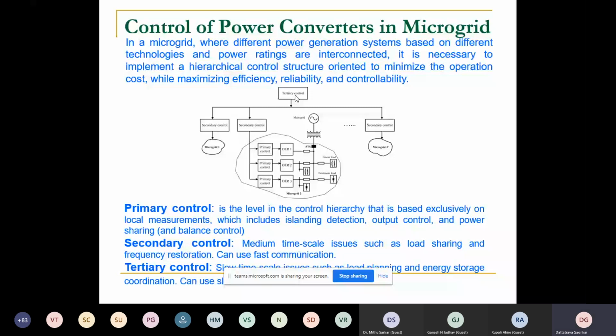So how do you do primary control? As you know, power electronic based DG systems need external control. Power electronics do not have inherent characteristics for controlling active and reactive power, whereas a synchronous generator has its own inertia and, by natural droop, is able to adjust the voltage and the frequency. That is not there in power electronics, so you have to design it. We'll look into the primary control.